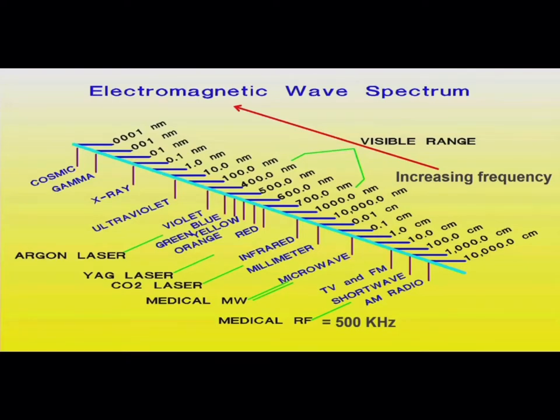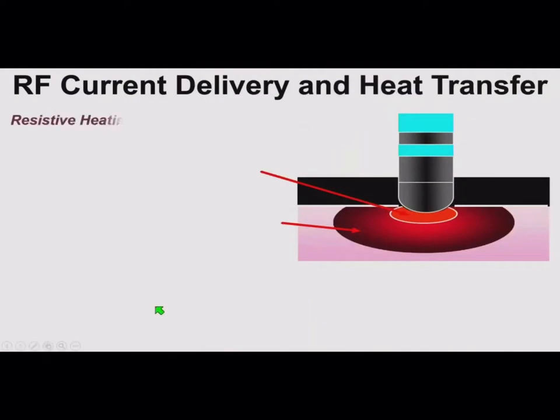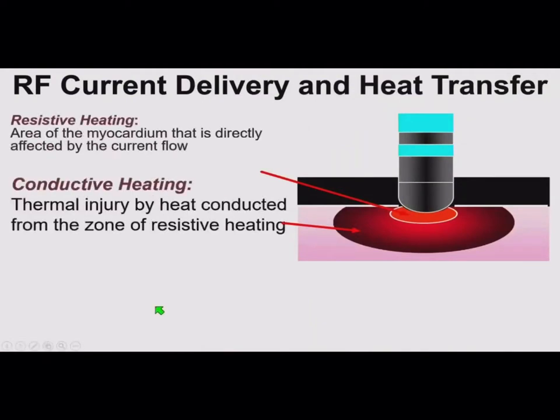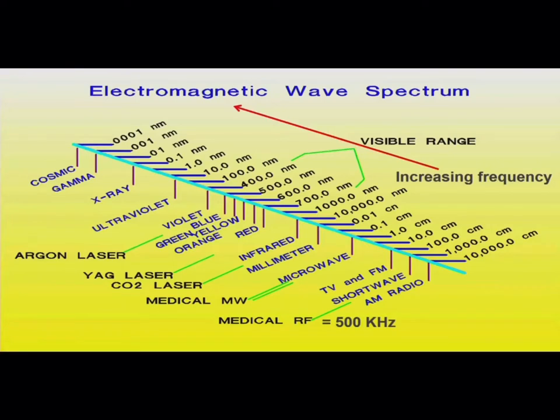So this is the electromagnetic spectrum. Remember that high-frequency radiation — things like x-rays — pass through tissue. When we're ablating tissue, we want to heat it. We essentially want to heat the water in the tissue, so we use generally lower frequencies. For RF ablation, it's generally about 500 kilohertz, which is somewhere between AM and FM. People don't always realize it's a lower frequency waveform. Laser ablation is also used — that's more in the infrared spectrum — but medical RF is about 500 kilohertz.